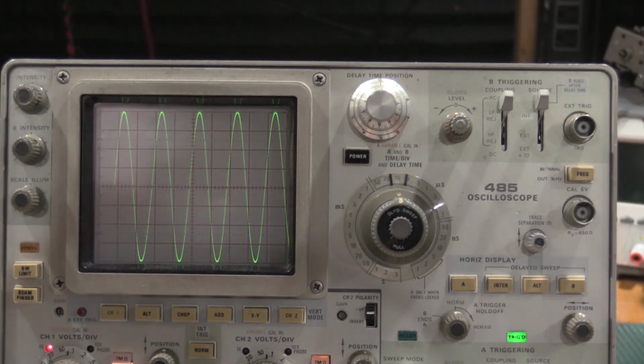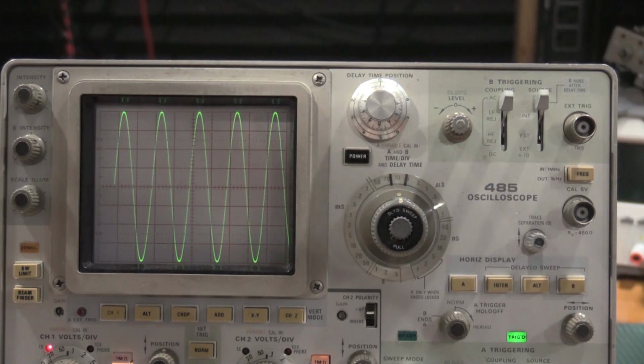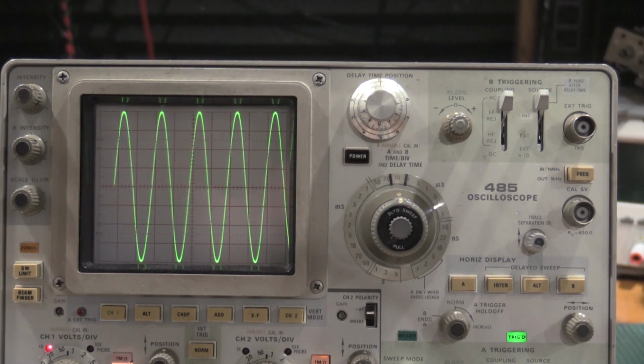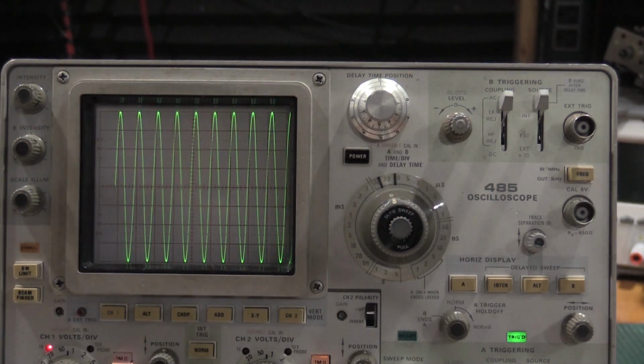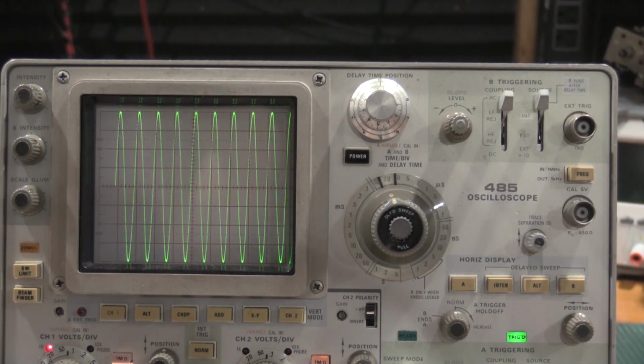That just came up recently during the calibration. I did check the signal source. This is not a signal source problem, so this is a triggering problem. I have a couple of things to check. I'm going to reseat a bunch of transistors on the sweep board because the triggering actually goes through the sweep board up to the top board. But that does seem to be where my problem is going to be. And it doesn't change anything if I change the time-base settings, which is fine.